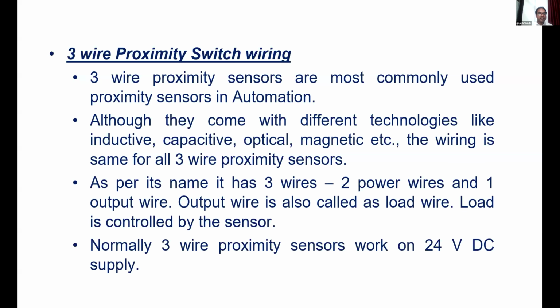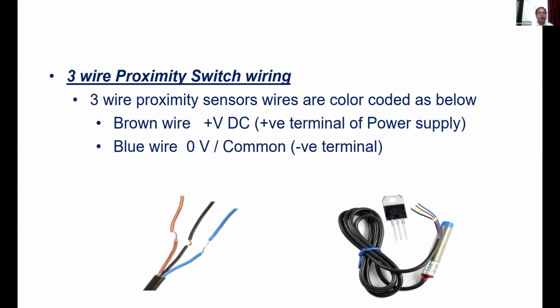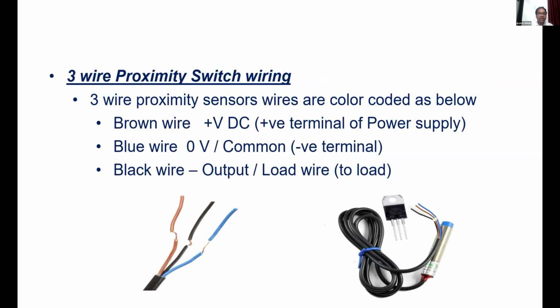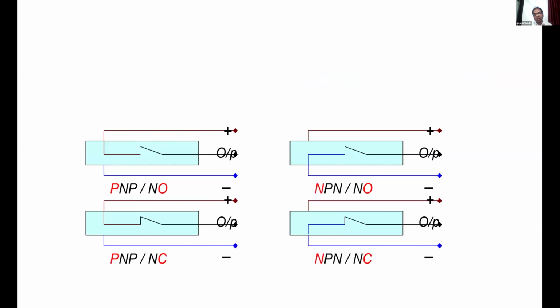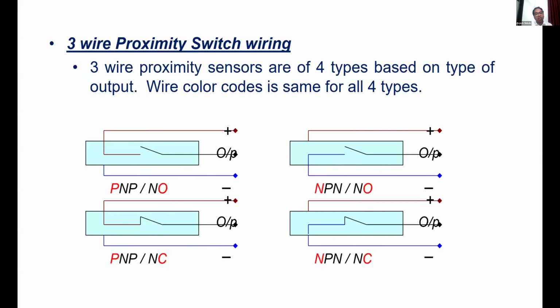Now, next we can see here, I have taken the next example of sensor, that is the 3-wire sensor, which is the most commonly used sensor, guys. In industry or in agriculture automation, the commonly used sensor is a 3-wire sensor. It has 3 wires. The first wire is the brown wire, the second wire is the blue wire, and the next one is the black wire, that is the output wire. Suppose you want to connect the output, we will connect the output to the black wire only.